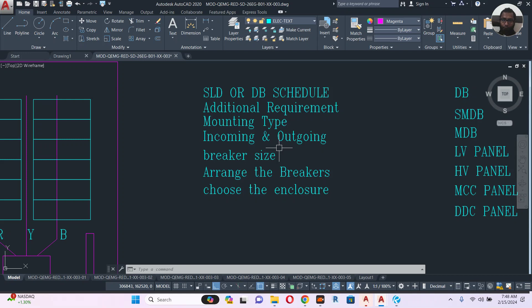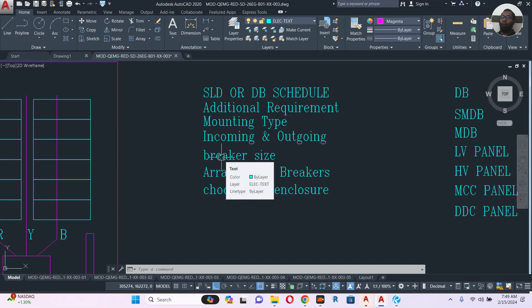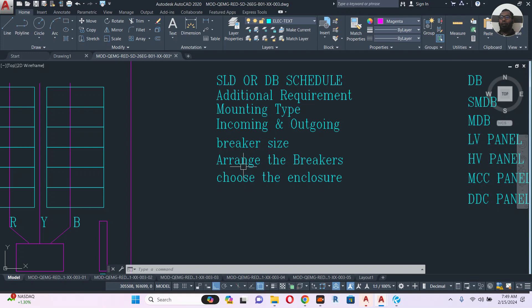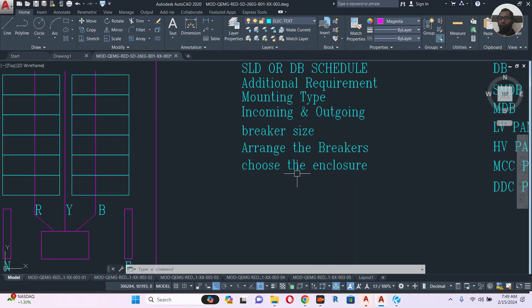You also need to know the breaker size. For example, if the SLD shows 63 ampere, you have to check whether it is a TP breaker, TPN breaker, or TP breaker with shunt trip, and find its center-to-center dimension. Once you know the dimensions, you can arrange the breakers and then determine what size of enclosure you need. Then you choose the enclosure — that's all, the panel is ready.